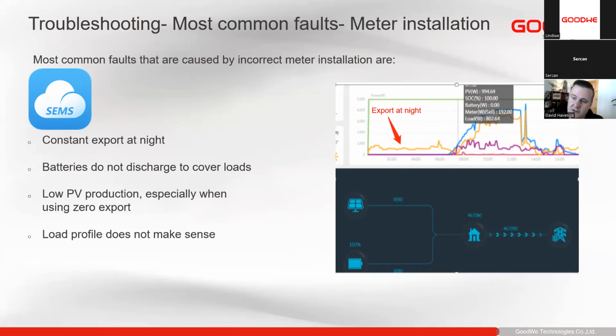And also if we're using zero export, like we need to in some countries, we'll see almost no PV production whatsoever, maybe only for charging of batteries. But in this case, the batteries would be full. And as well, you'll see there's no load. It shows the load profile very low, at 0 at night, because the consumption is counteracting with the meter data.